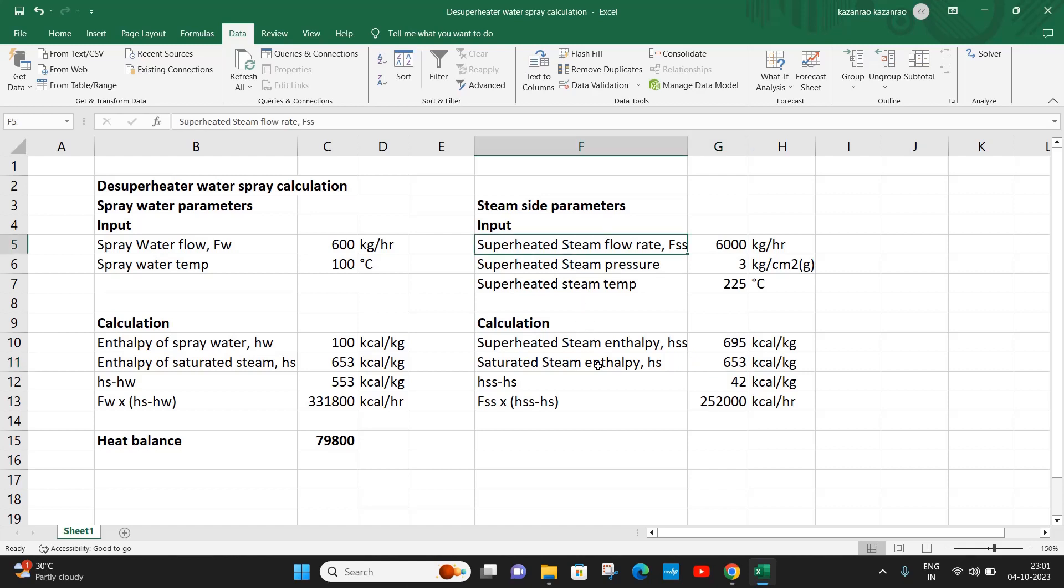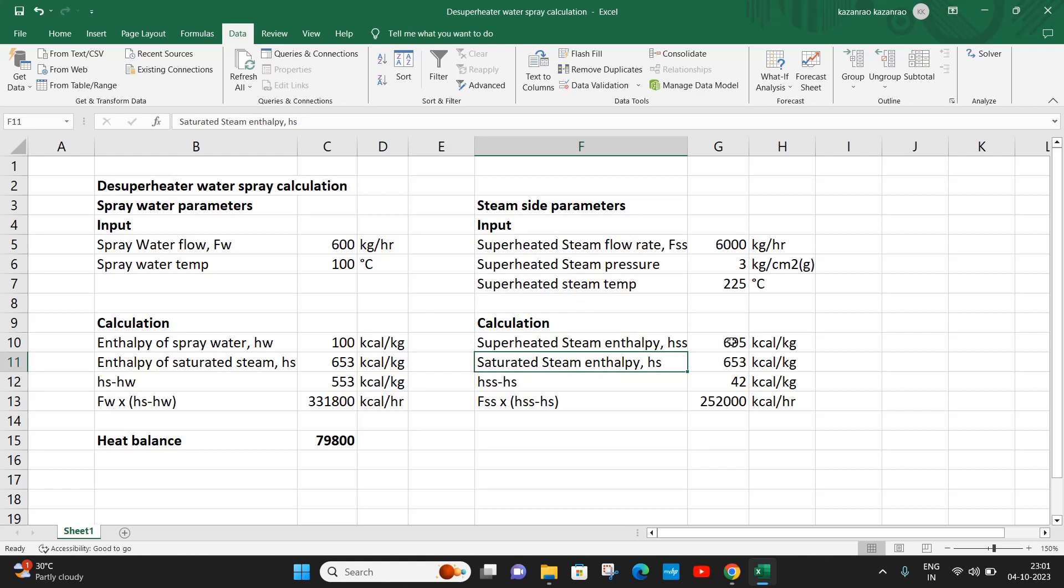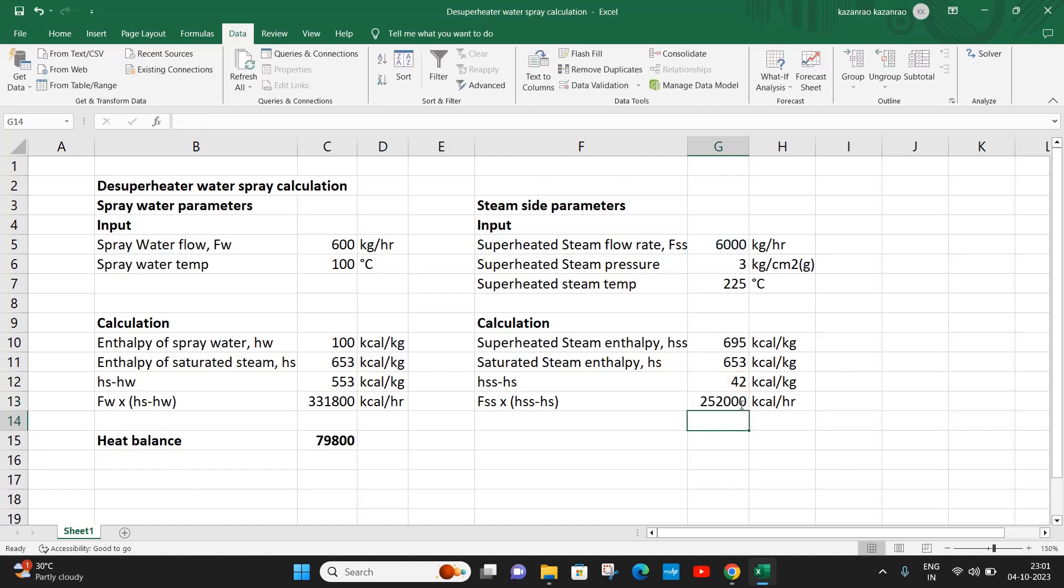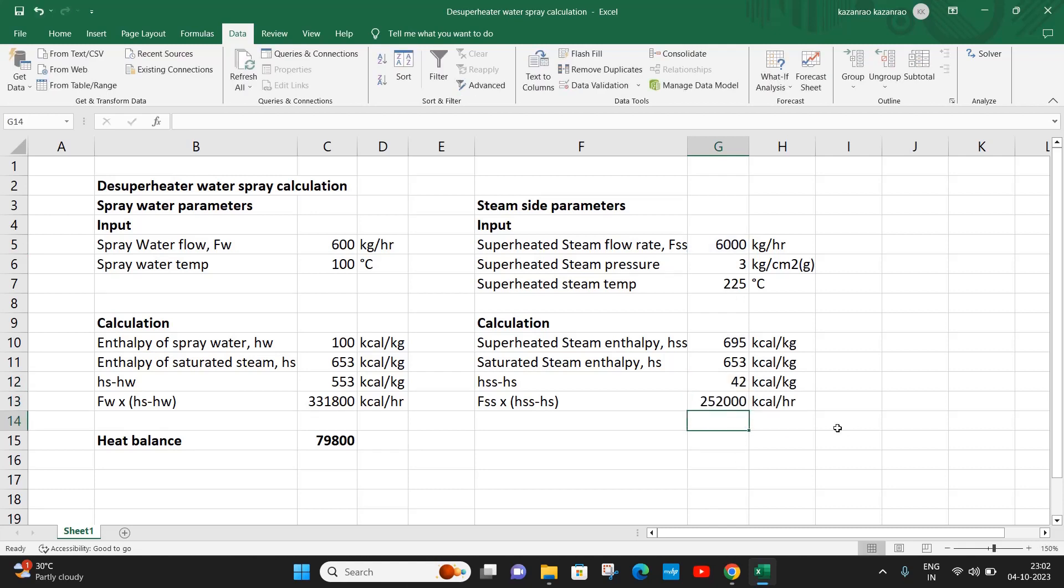So it is 42 kcal per kg difference, or the total heat that has to be removed from the superheated steam is 252,000 kcal per hour. This is calculated by multiplying the flow rate with the difference of superheated enthalpy to saturated enthalpy. The difference is 42, and then this 42 is multiplied with the flow rate to get the heat that has to be removed from the superheated steam.